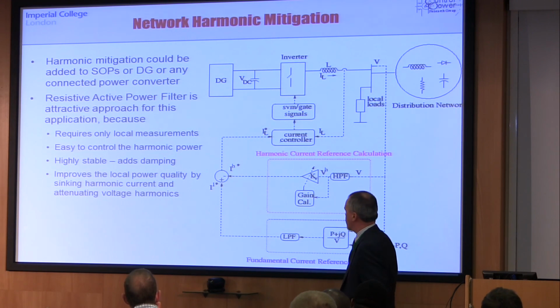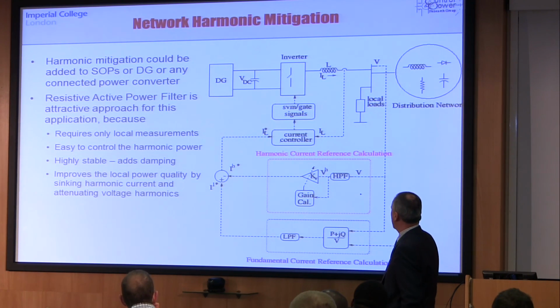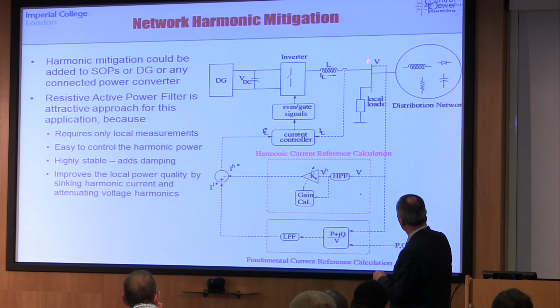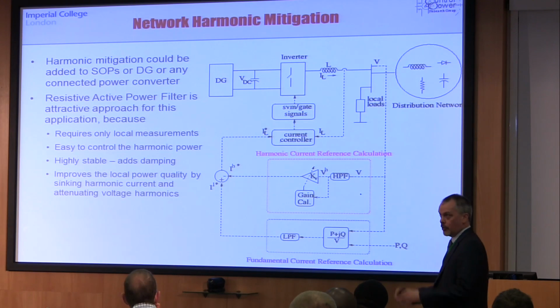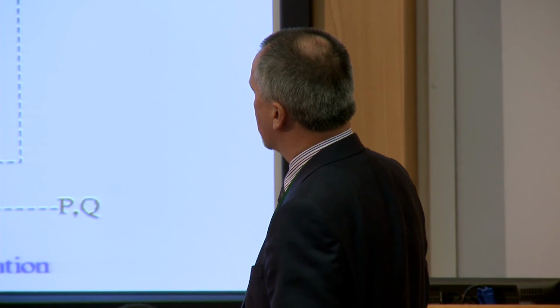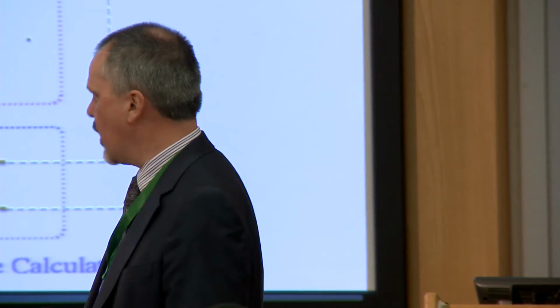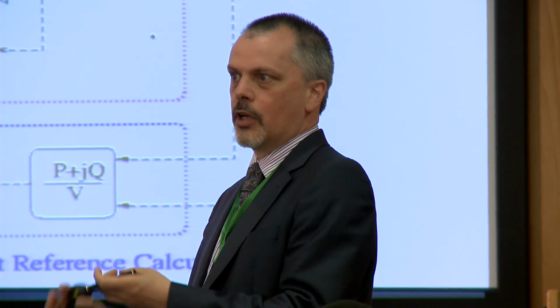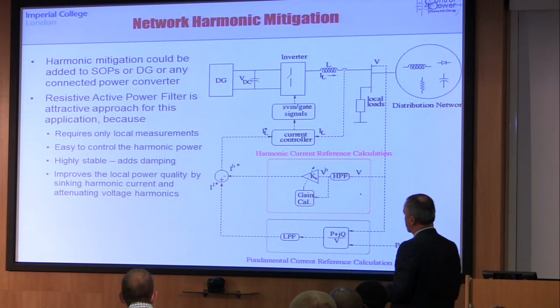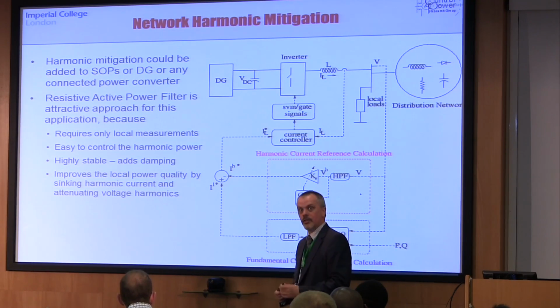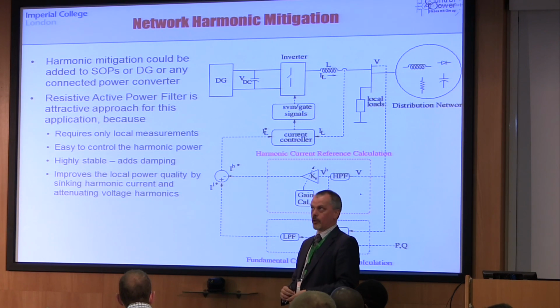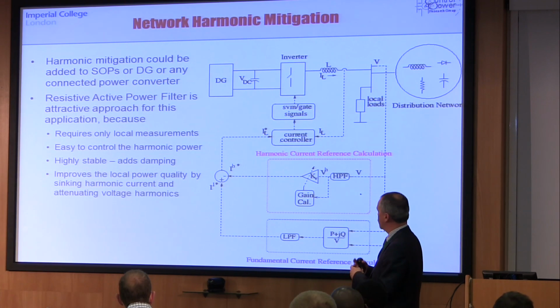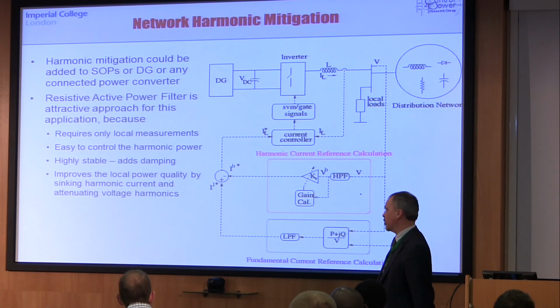And this is a set of control loops one can add to an inverter to measure the harmonic voltage, synthesize a reference current for that harmonic based on an assumed impedance, and add that into the current controllers. And I quite like that because it's a way of adding a sink of harmonic currents in a way that adds damping to the network. And it's also a way which is understood by power systems engineers. Now they have an additional set of harmonic impedances, which are harmonic resistances, to add to a harmonic load flow.